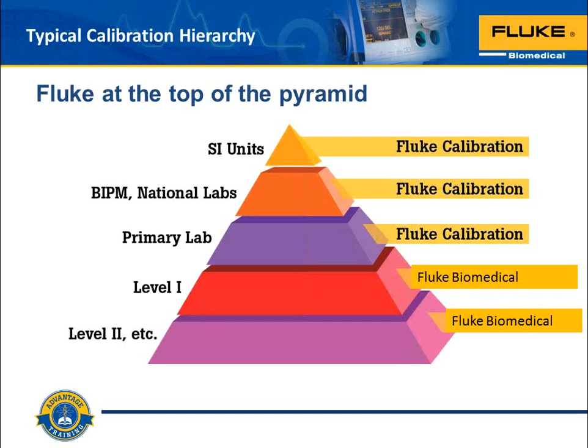So here's another way to look at it in terms of Fluke Biomedical. Let's take an electrical safety analyzer, which includes DC volt measurements. How are we traceable within Fluke? Because at Fluke, one of the things that we do is we create the primary DC volt using this Josephson's array that you see in the upper left-hand picture. That Josephson's array is the primary standard. And we use transfer standards that we calibrate against that Josephson's array to go and calibrate our Fluke calibration, our FCal tools, which are used in our production line and our service depots all over the world to do the calibration on an electrical safety analyzer, for example.